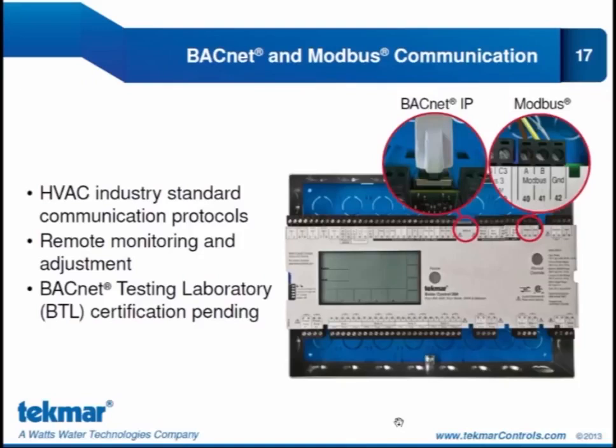The BACnet IP connects from the RJ45 port on the top of the 284 control. The Modbus connection is through 3 terminals, terminals 40 to 42. The connection is with a shielded twisted pair with a signal ground. So the shielded twisted pair are in terminals 40 and 41, Modbus A and B, and then we have our ground wired into terminal 42.